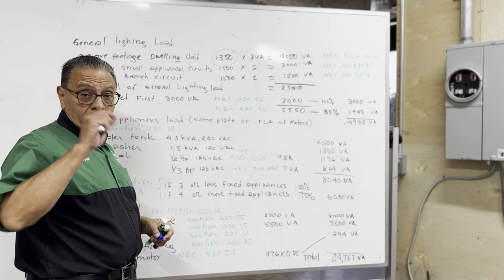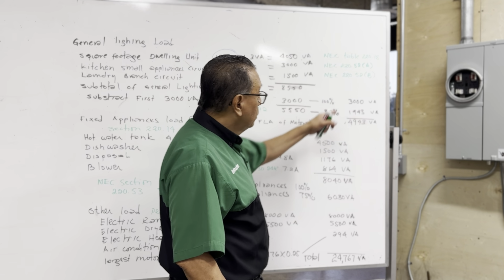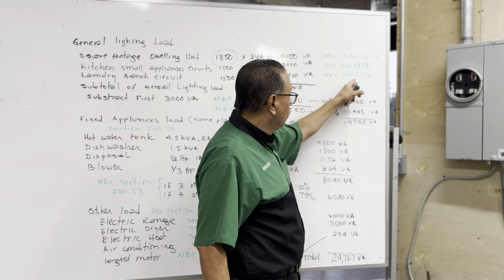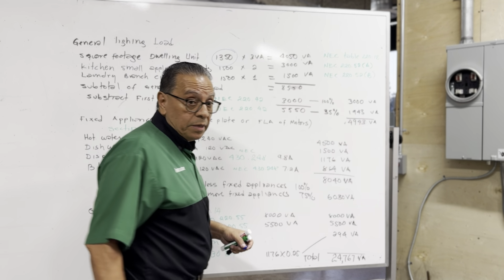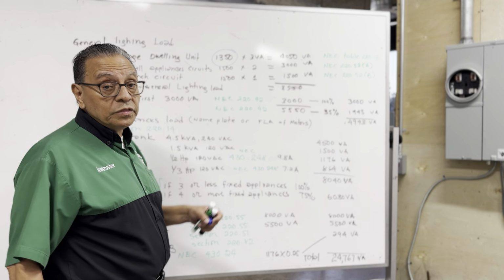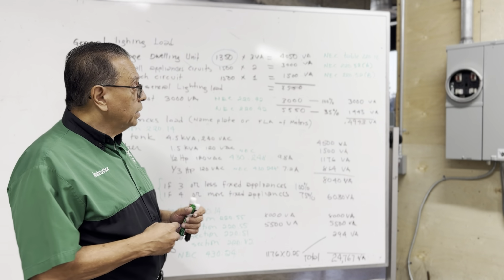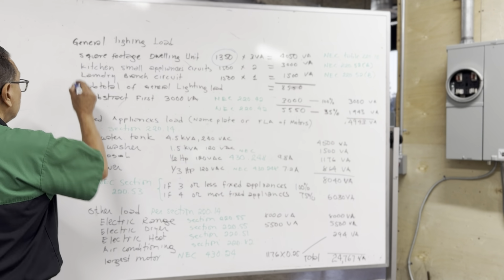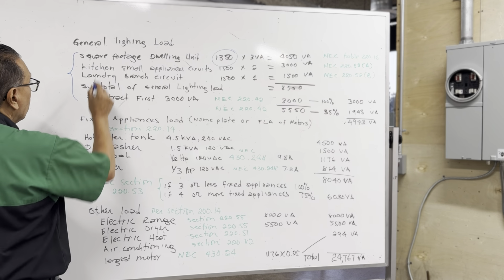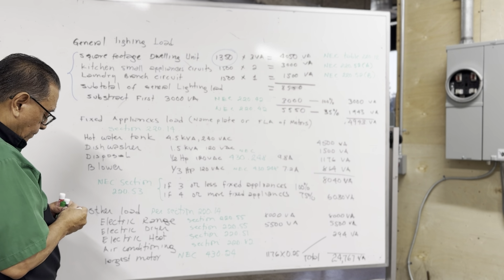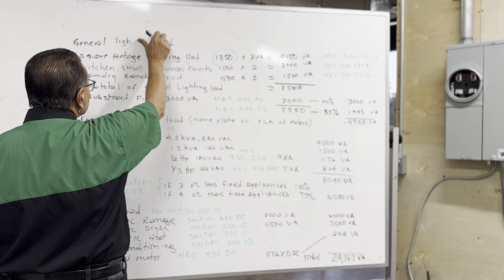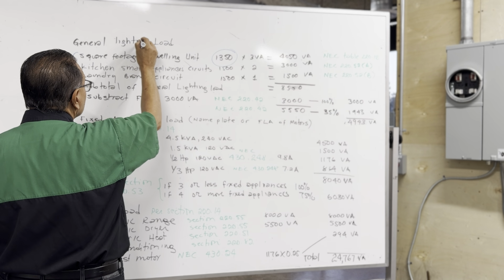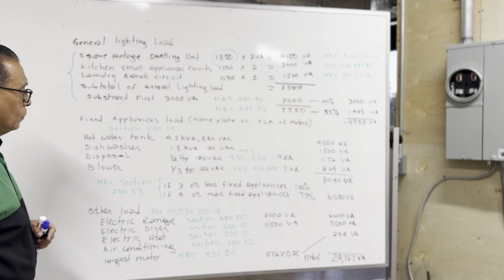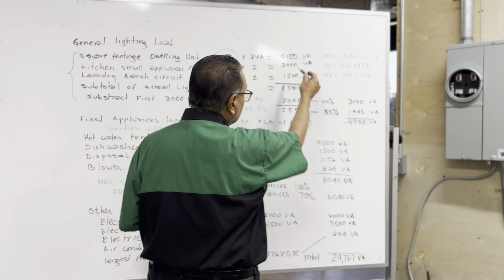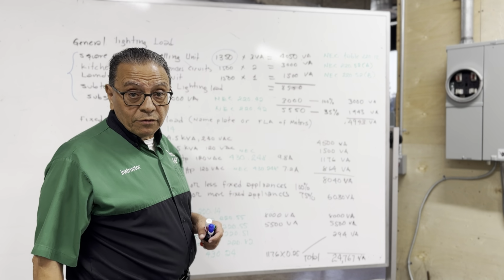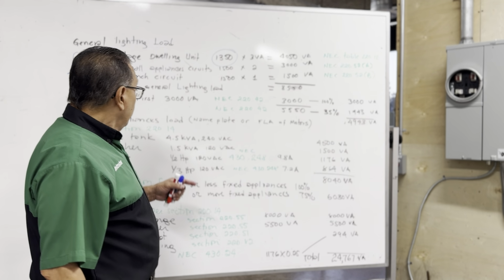And the NEC in Article 220.52(B) is asking me to reserve a 1,500 volt ampere branch circuit for the laundry. And all of these together are known as the general lighting load. The general lighting load. So when I add all of this, I have a total of 8,550. Okay.